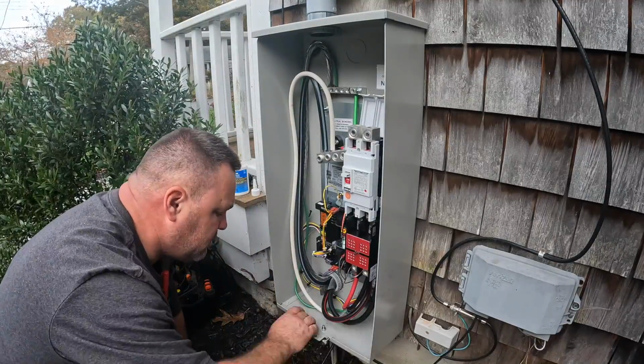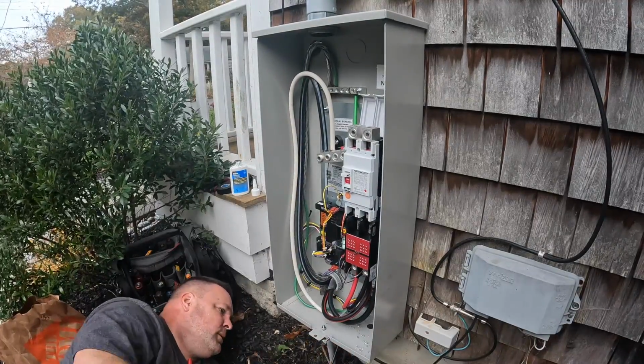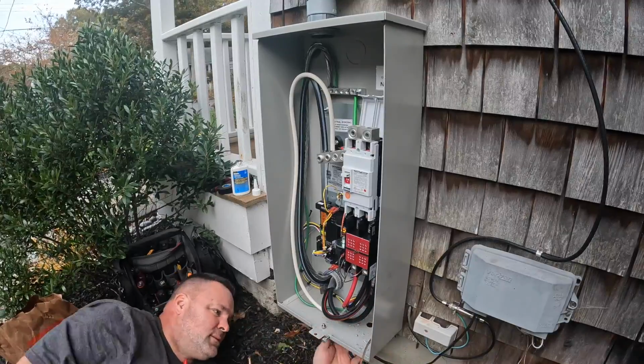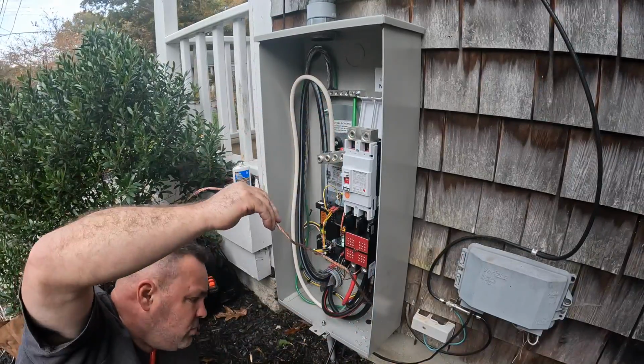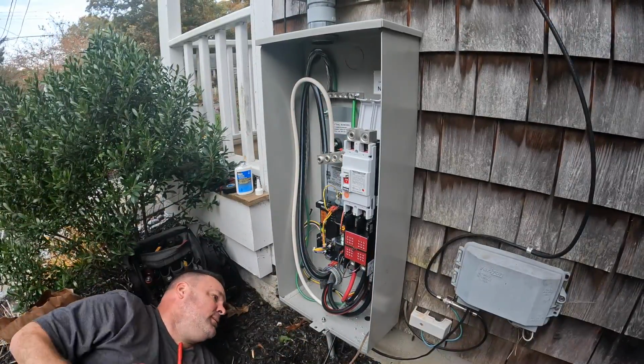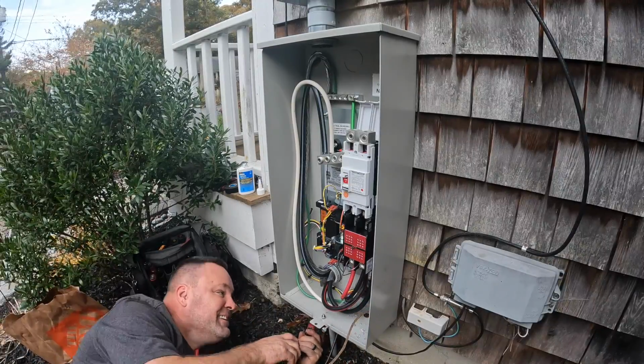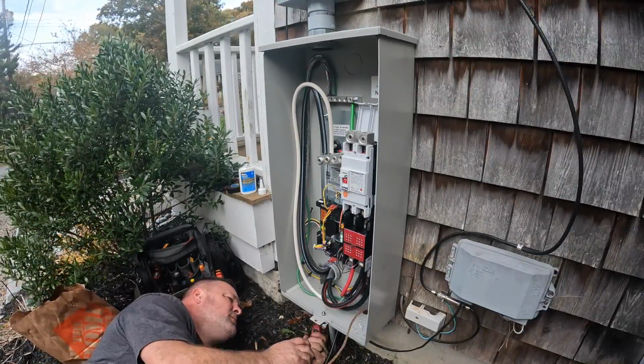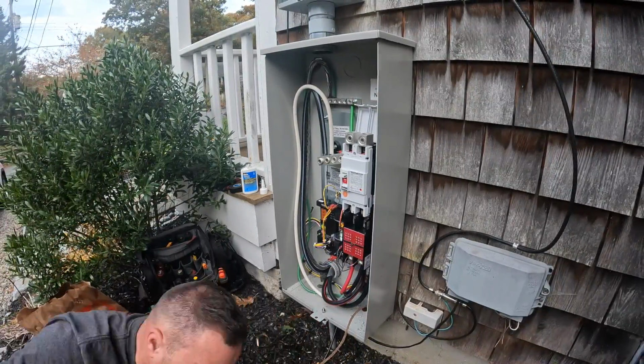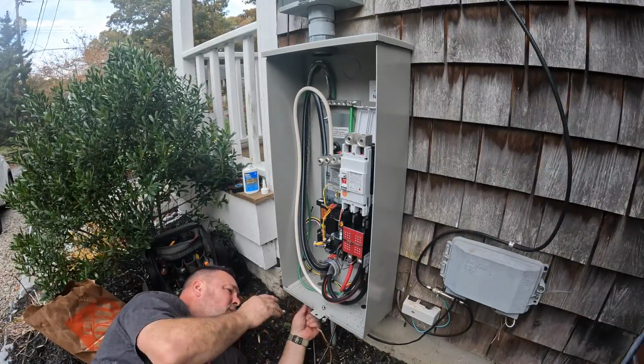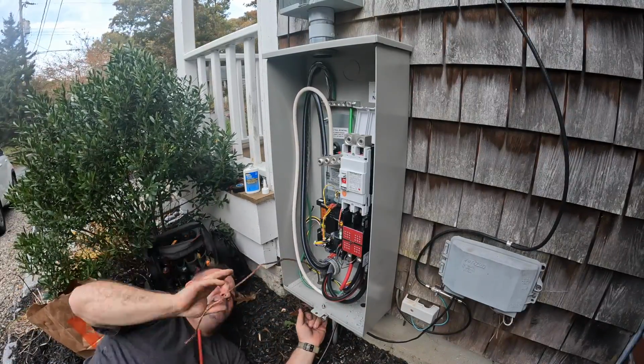So the last thing I had to finish here was the grounding electrodes. I had one ground rod number 6 cable. I had another number 6 cable going to that equipment grounding block on the side of the panel here. And then, of course, my water main, which I had to extend, also comes into the bottom of this panel.